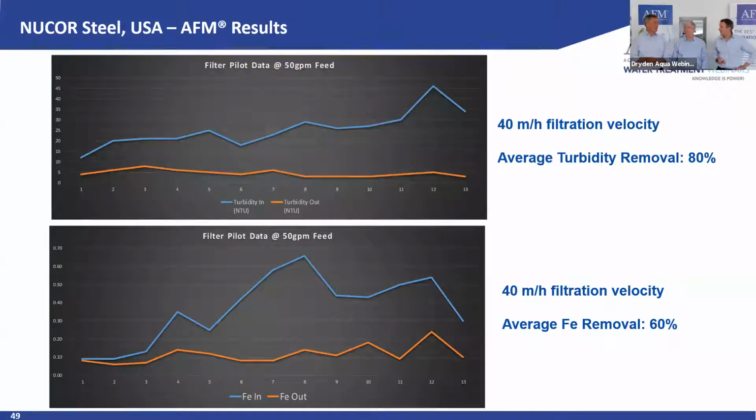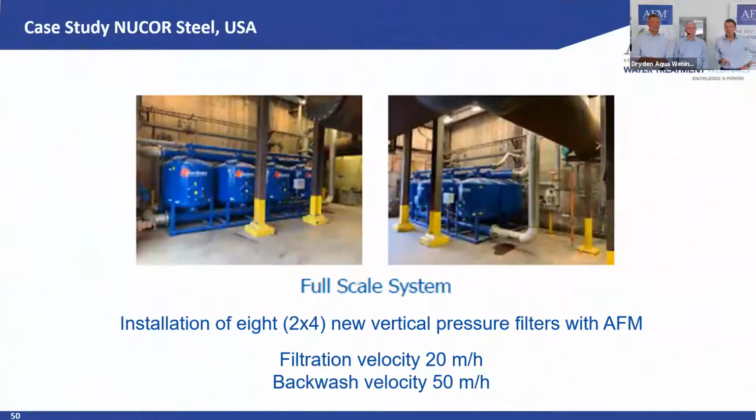This is unbelievable. So the customer was extremely happy, and of course that was no surprise. They then followed with the full-scale implementation. They installed a total of 8 filters, 4 filters in a row, vertical pressure filters with AFM.